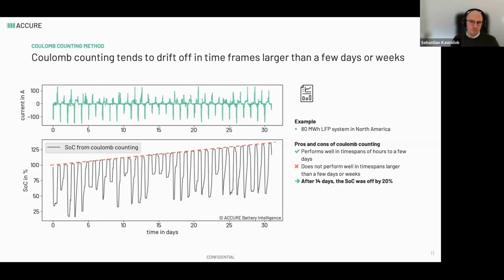This then translates to a pretty significant error in the SOC estimate, which is in this case up to 20% after only 2 weeks time. And as you can imagine, if you're relying on that SOC to trade your energy, that is not a good thing. So you need to recalibrate at certain points.